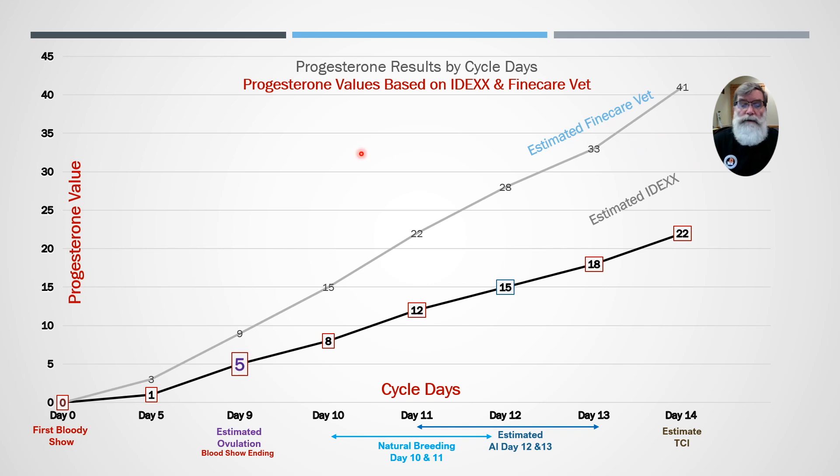As you get higher in the ranges the bias difference increases from low end to high end, which is to be expected. To make it simple, we run correlations — hundreds of serum tests between an IDEXX-related instrument and the Finecare Vet — to determine where these numbers come from. We take the correlation data, know what the differences are, and put it all in a timing chart. That nice colorful timing chart comes with any instrument you buy from us.